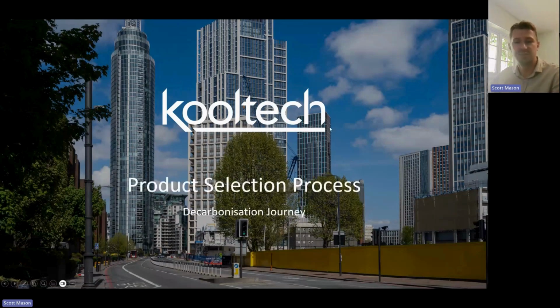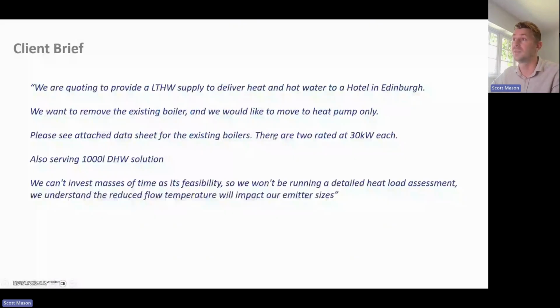So this brings us on to, now we've done a bit of groundwork, the selection and sizing process. The things to consider when applying an air source heat pump to your building. It's going to be focused on the Chavar, because of course that was the unit that accompanied us on the roadshow. But basically, what we're going to do is run a size and selection for a project. It's going to be a small commercial heating and hot water solution, and we're going to look at some schematics of how we can address this scenario.